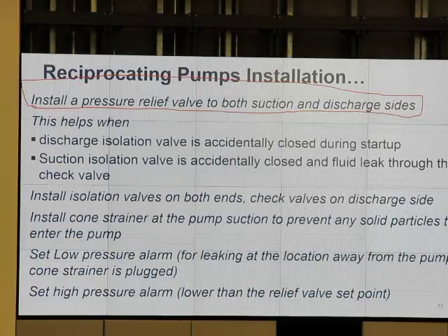It's not quite the same for the centrifugal pump, right? Centrifugal pump, if you close the suction side, you close the discharge side, you spin it, it just keeps spinning. If it's too long, yes, you damage the pump. But if it's 2 seconds, 3 seconds, it's no problem. But with this pump, if you close the suction, you close the discharge, and you try to turn the pump on for 3 seconds, it crashes. Don't do that.